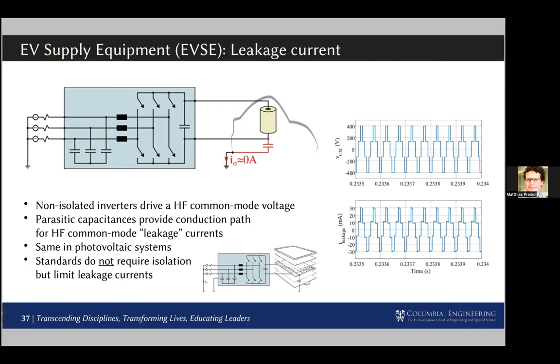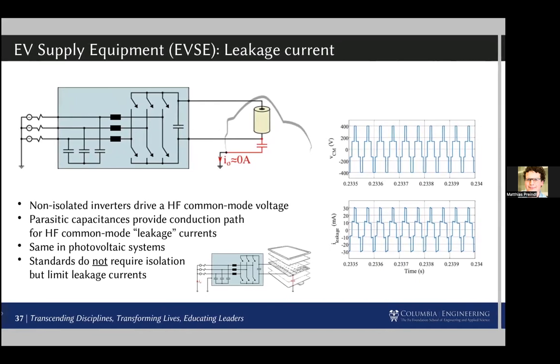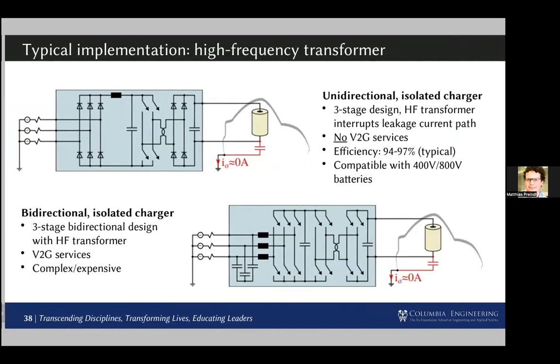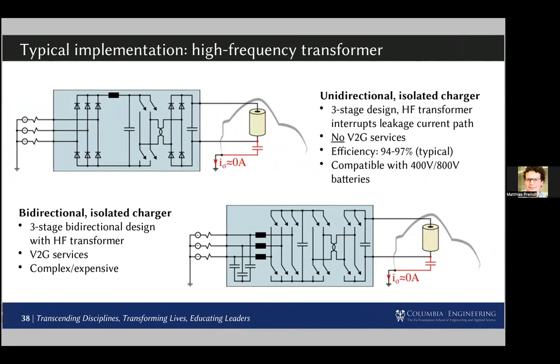So there is a potential ground loop between the grid and the battery. This is the same behavior that happens in photovoltaic as well. If we don't manage this ground loop, we can get potentially quite high leakage currents to ground, because the switches switch fast, and so even a small parasitic capacitance to ground provides a suitable conduction path. A common approach today is to simply put an isolation transformer, a high-frequency isolation stage, between the grid and the battery. That's one way to go about it.